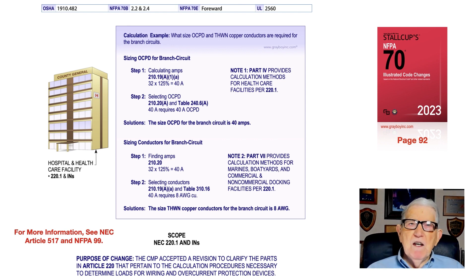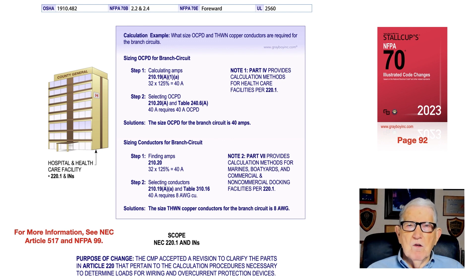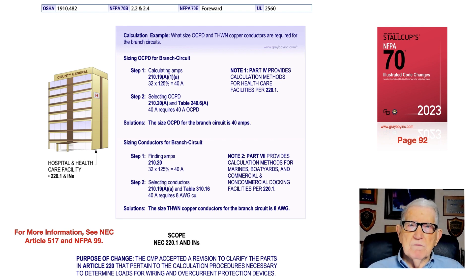For more detailed information, see NEC Article 517 and NFPA 99. In the boxed-in information, we're going to do a calculation for a branch circuit — sizing the overcurrent device and conductors. Sizing the overcurrent device: step one is 125 percent of 32 amps, which is continuous, and that would be 40 amps.